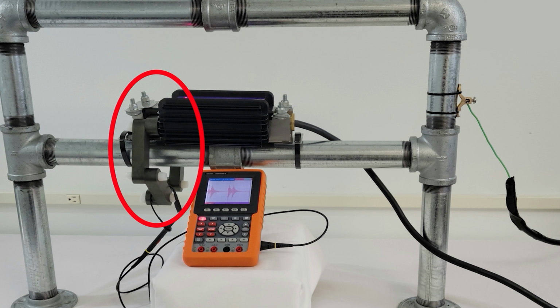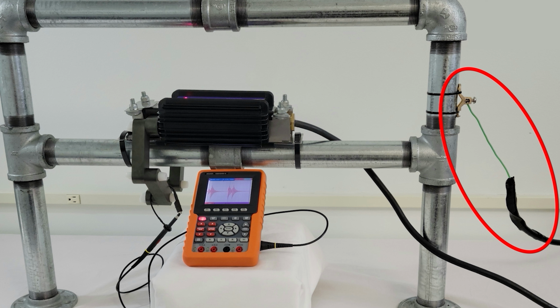Now we'll install the ferrites around the pipe on this test stand, which has been intentionally set up in an electrical loop. Since all plumbing systems are grounded, we connected the stand to earth ground. Next, we'll repeat the same scope measurements and compare them to the off-pipe measurements.